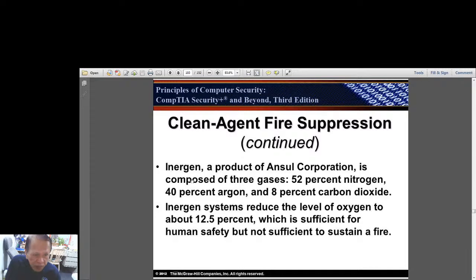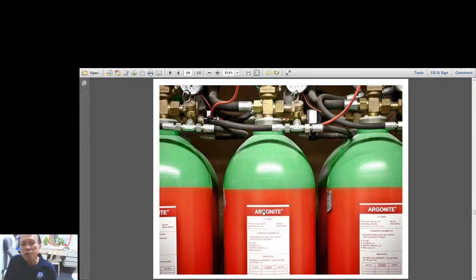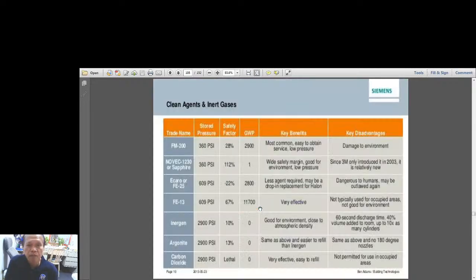Clean agent fire suppression. Inergen is a third one. Inergen is a product of Ansul Corporation. It is composed of 3 gases, 52% nitrogen, 40% argon, 8% carbon dioxide. Inergen systems reduce the level of oxygen to about 12.5%, which is sufficient for human safety, but not sufficient to sustain fire. So that's how this Inergen works, no? And here is a picture of that argon gas or argonite gas, which is also an inert gas. And here is a tabulation matrix prepared by Siemens showing some of the different agents. Let's take a look at them.